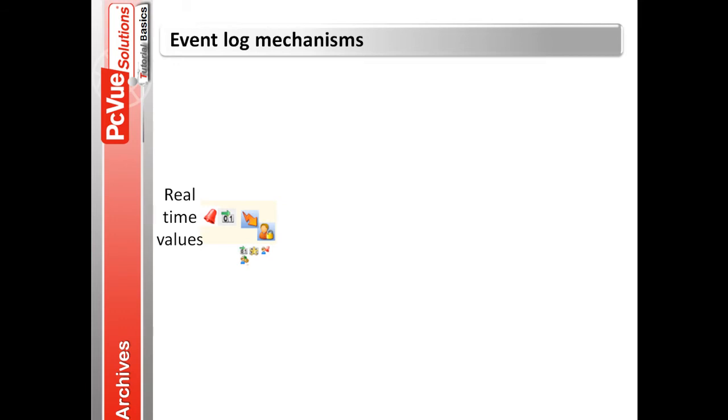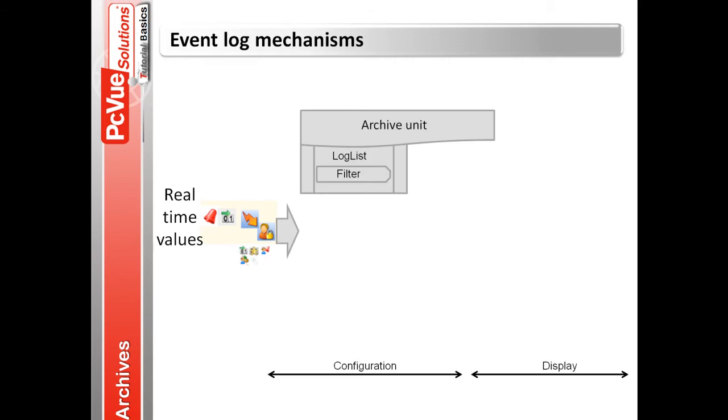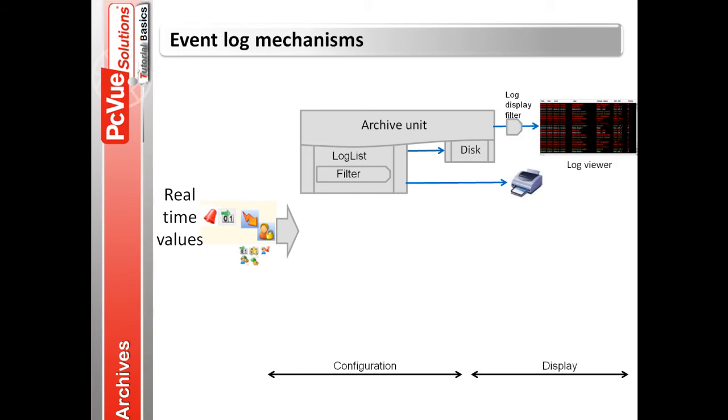A log list is attached to a specific archive unit to record as well as to print output events and to display with a log viewer. To make a variable, bit or alarm eligible for recording through log list filters, we select in its configuration the property LOG. All user actions are eligible for logging without requiring any configuration.